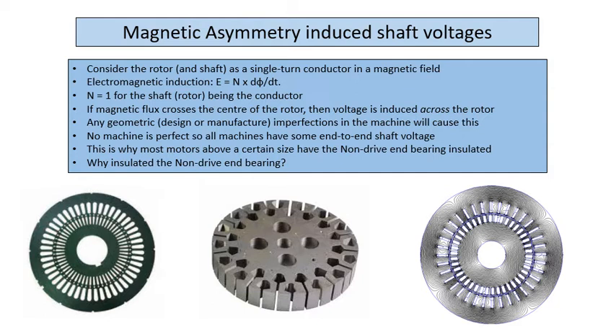Now, why would one bother about earth brushes anyway on a motor? Why not just insulate both bearings and just let the shaft float? Well, you'd have an electrostatic voltage generated on that as well. So you need to do some form of earthing. So the reason why they often earth, for instance, on an EX application, you'll have to ensure that you don't allow a floating rotor system to go up into electrostatic voltages and then have continuous breakdown. Even though that continuous breakdown might not destroy anything over time, it could be a risk in terms of explosive environments and things like that.